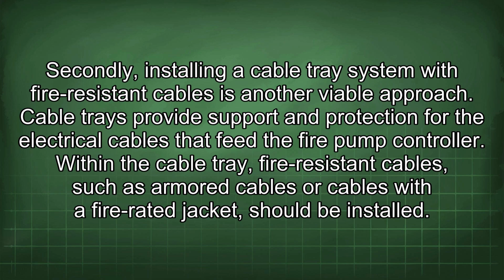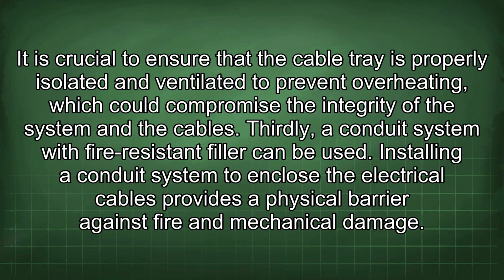Cable trays provide support and protection for the electrical cables that feed the fire pump controller. Within the cable tray, fire-resistant cables, such as armored cables or cables with a fire-rated jacket, should be installed. It is crucial to ensure that the cable tray is properly isolated and ventilated to prevent overheating, which could compromise the integrity of the system and the cables.